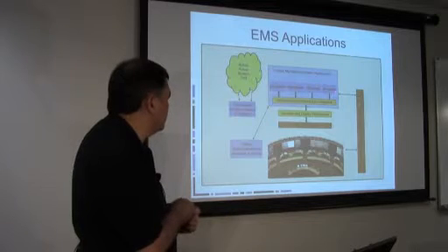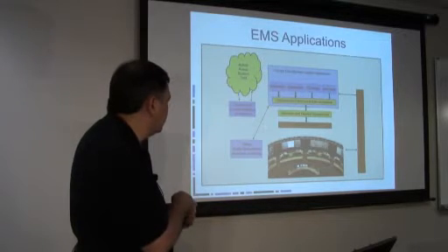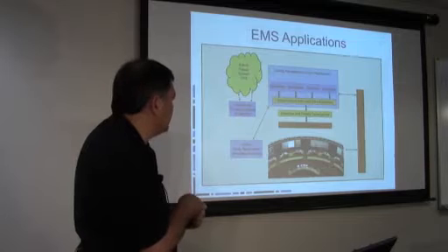And in the simulation mode, we actually cut the tie to the real power system, and then the simulation engine stimulates all of these applications as if they are running in real time. So if we're running in simulation mode, we would actually be running in a separate control center from the real one. And that's what we call a replica simulator, where you literally replicate all of the consoles, even the projectors, the computers, and you stimulate that from a mathematical model.